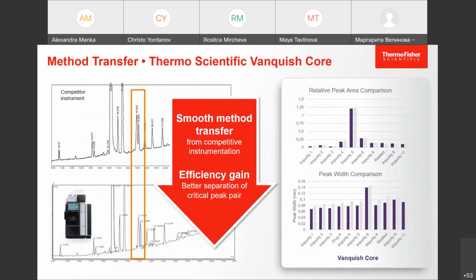Here I want to show you only one example of a method transfer. This is a chromatogram measured on a competitor instrument, and the same chromatogram measured on the Vanquish Core. The relative peak areas are almost the same on both systems. But when you look at the peak width, you see that on the Vanquish Core, all peaks are narrower. And with that, the sensitivity and the resolution increase. So you get better separation of the critical peak pair.